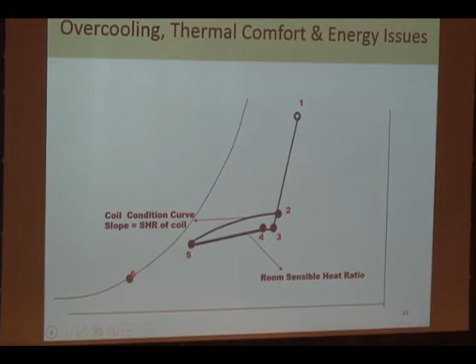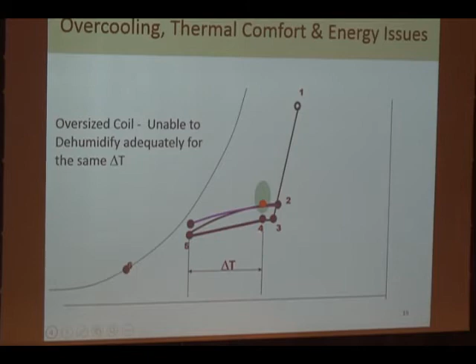If we have an oversized coil, we have a situation where the temperature is properly managed and controlled, which is the strategy adopted in most building systems, but the humidity is not. So the space levels go up in terms of its humidity - instead of 4 being here, you get to see it over there. If you want to address the humidity, we overcool, and that's where the coil comes off, and we cannot or don't use reheat because it's not sustainable practice. Most places would not allow using reheat for comfort air conditioning. We leave it at that.